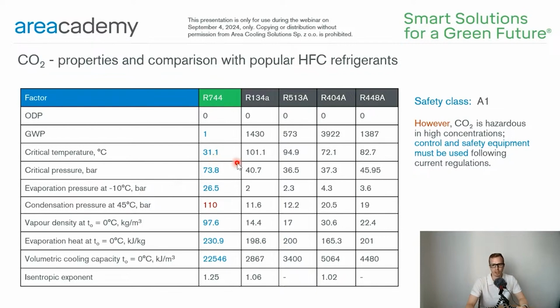And as you can notice, the CO2 refrigerant has much lower critical temperature compared to other refrigerants and much higher critical pressure. Another interesting fact is that the evaporation pressure at minus 10 degrees Celsius is even higher than the condensing pressure for all other refrigerants. Accordingly, the condensing pressure for CO2 at 45 Celsius degrees is multiple times higher than for HFCs. As you see, CO2 is a very dense refrigerant, and this makes the compressors much smaller than those dedicated to working with HFCs. The fact that CO2 is a very good refrigerant is evidenced by its high specific cooling capacity. The evaporation heat for CO2 has the highest value in the table, as you can see.